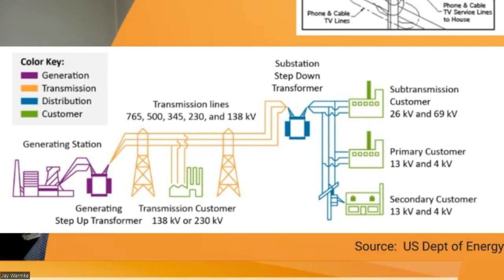Those very high voltage transmission lines are the tall ones you see driving along the highway. They can transmit at 765,000 volts, 500,000 volts, 345,000, 230,000, or 138,000 volts. The further the distance, the higher the voltage needs to be to minimize power loss between the generating facility and where it's used—sometimes as much as 300 miles. I checked the distance from our office to the generating plant here, and it's about 144 miles.